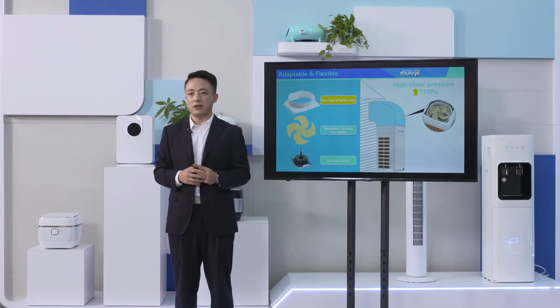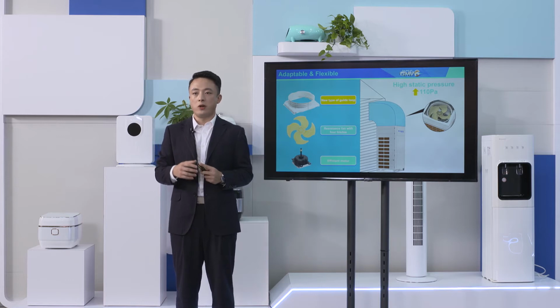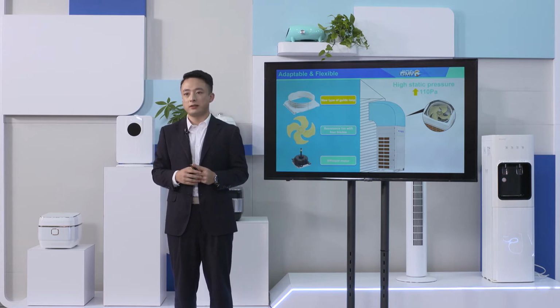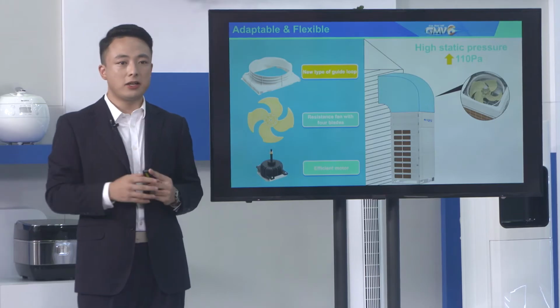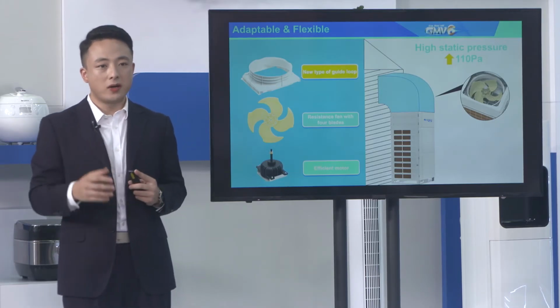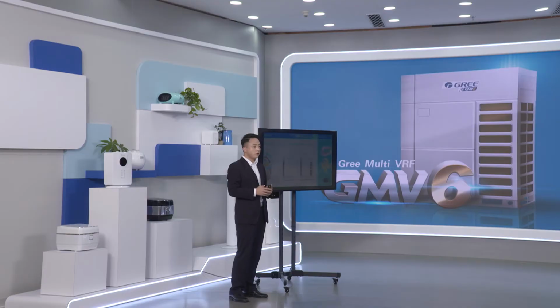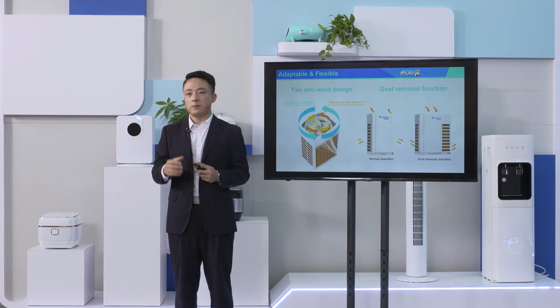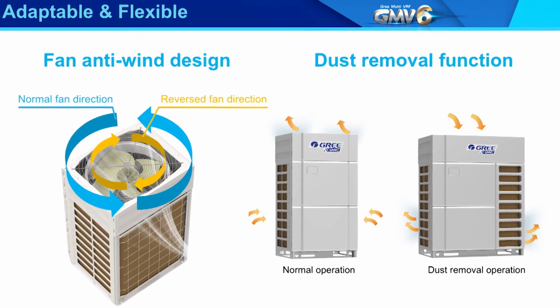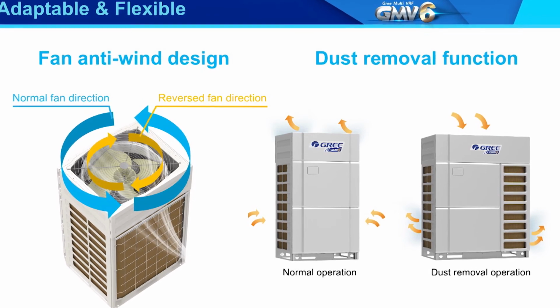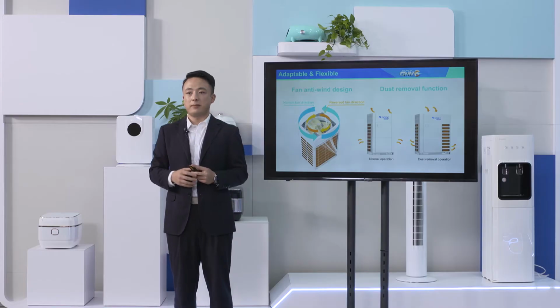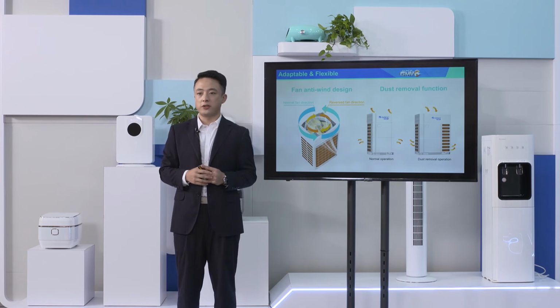The ultra-high static pressure design can be used in installations such as equipment rooms where external machines need to be connected to the air duct, making the application range of the unit more extensive. In order to enable the unit to adapt to changes of the environment, we adopted anti-headwind and automatic dust removal design for outdoor units. Once the fan is reversed by the wind, the unit will apply energy braking to stop the reverse fan, and then start up according to the normal procedures.